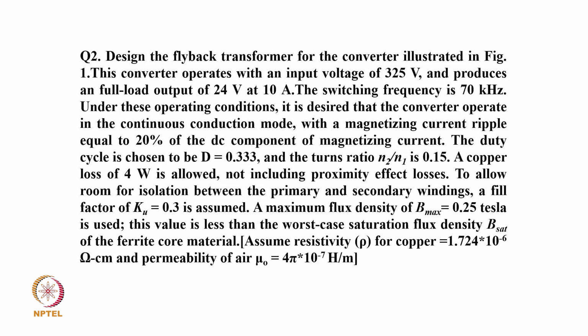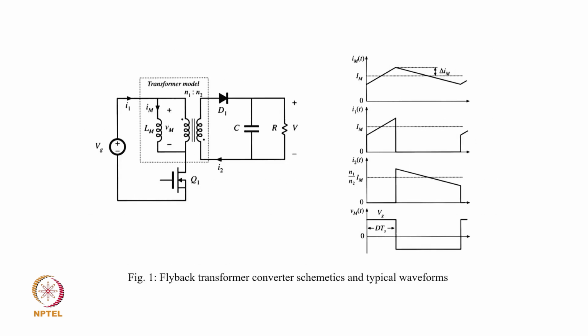A fill factor of Ku equal to 0.3, and a maximum flux density B max of 0.25 Tesla. This value is less than the worst case B saturation of the ferrite core. Assume the resistivity of copper 1.724 into 10 power minus 6 ohm centimeter, and the permeability of air mu0 equal to 4 pi into 10 power minus 7 Henry per meter. So these are the typical circuit of the flyback converter, schematic and waveforms.